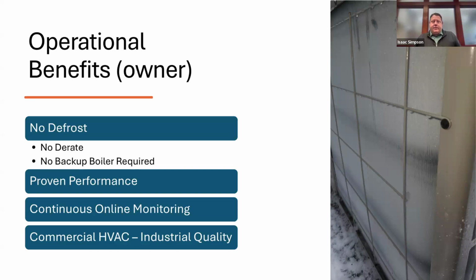Prior to this system coming onto the market, if we were looking at a heat pump, one of the big things we would have to deal with is defrost. After a certain number of hours of operation in heating, the system would naturally build ice on its outdoor coil and then have to stop operation and operate in a cooling mode to heat up and de-ice the outdoor coil, and then stop again and go back into heating mode. So there's a significant period of time out of each hour, maybe 8 minutes, 10 minutes, 15 minutes, depending on the system type and the coil circuiting, that the heat pump is not doing its job, which is heating the building.